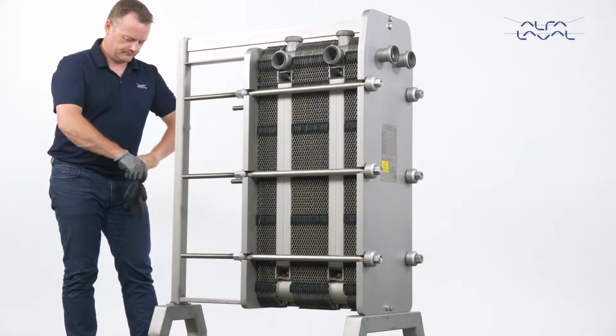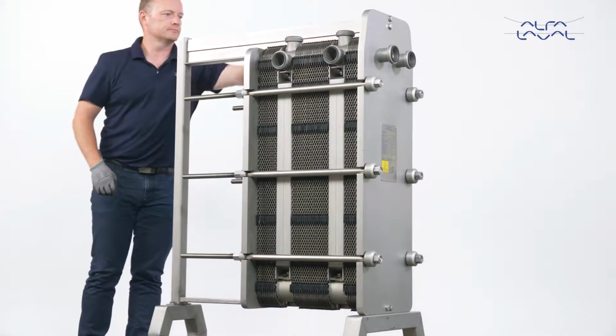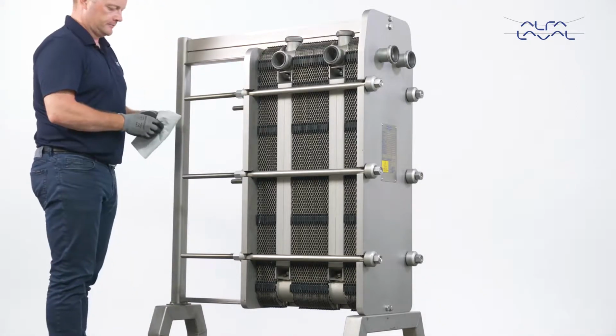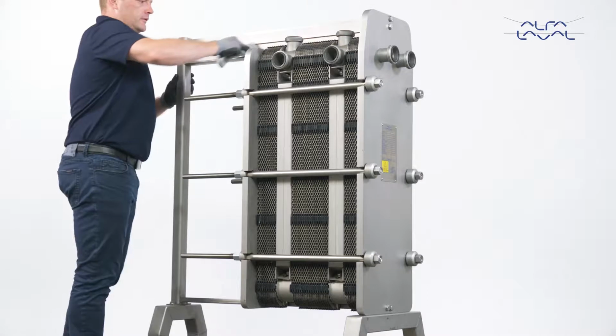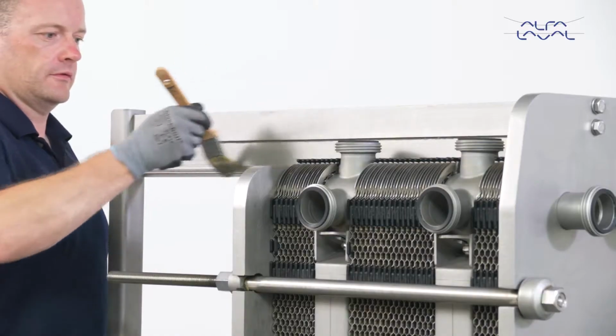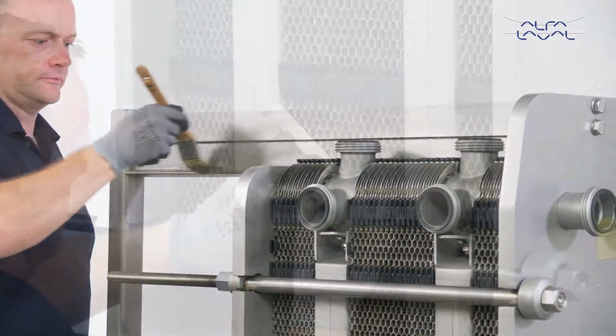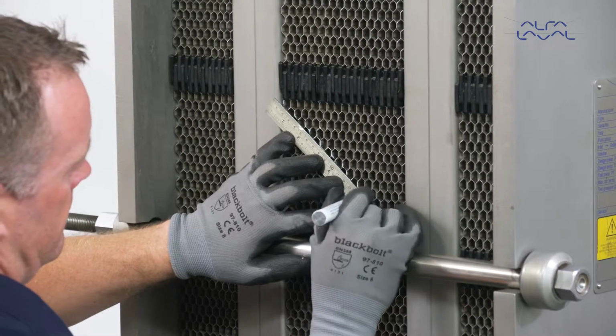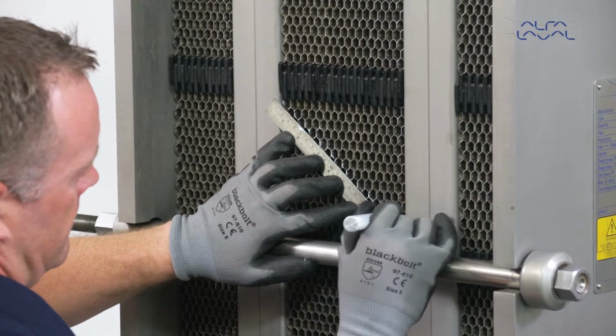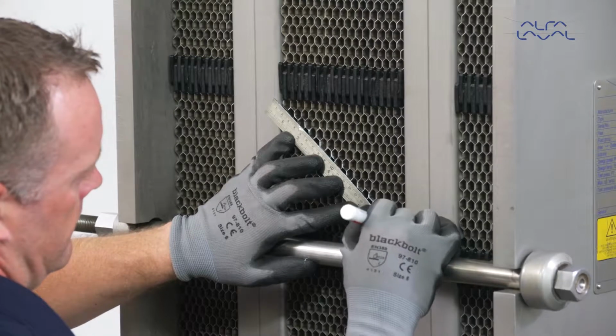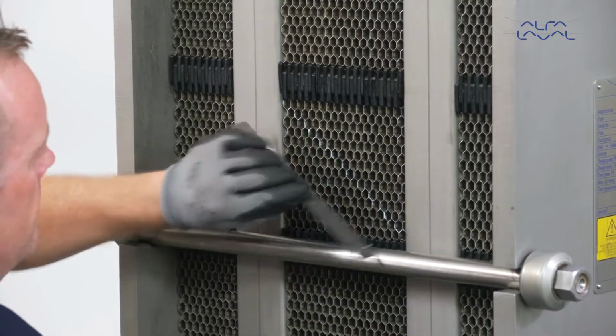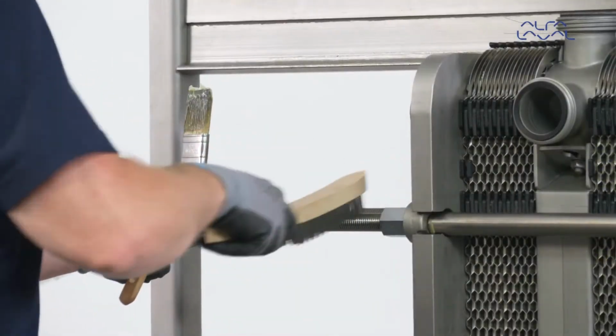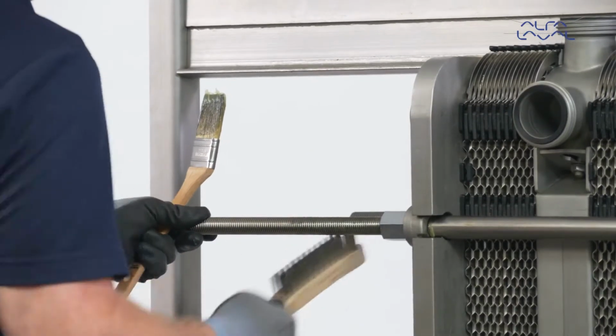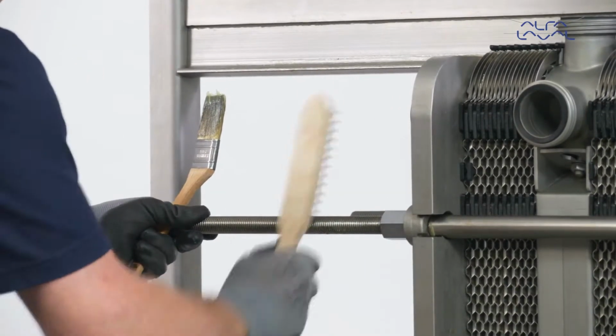First, inspect the sliding surface of the carrying bar. Wipe it clean and apply grease. If you intend to remove the plates to change the gaskets, we recommend that you mark each plate pack. Brush the threads of the tightening bolts with a steel wire brush and grease the threads before loosening the bolts.